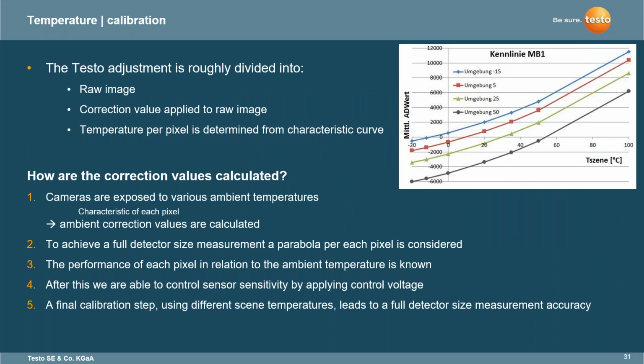So the Testo adjustment is roughly divided into the raw image, the correction value applied to the raw image, and the temperature per pixel determined from the characteristic curve. My apologies, this is in German, but it gives you an example of exactly how this is calibrated. We're generally taking 3 to 5 points of calibration when going through the factory calibration, and we're actually taking imagers and putting them into an environmental chamber.